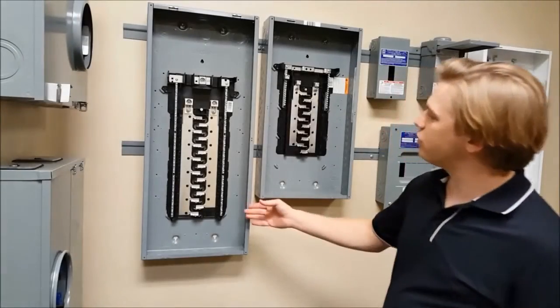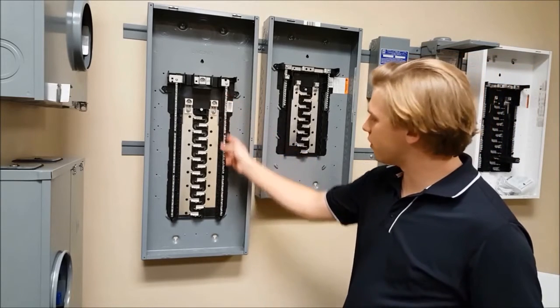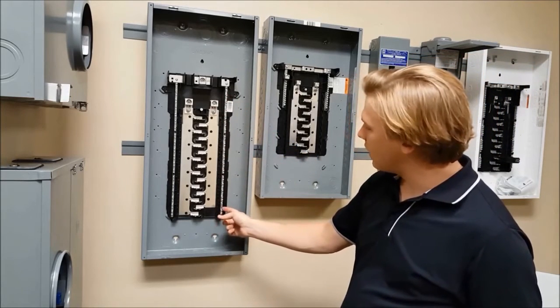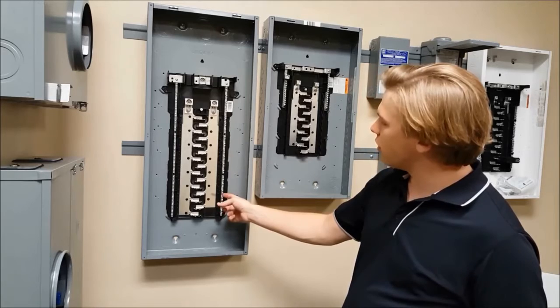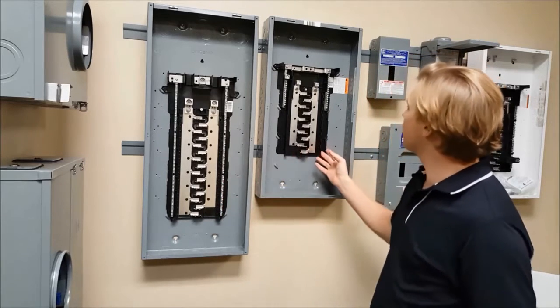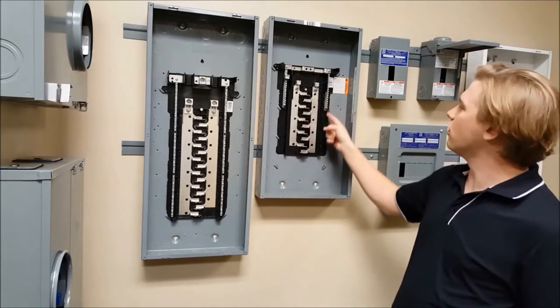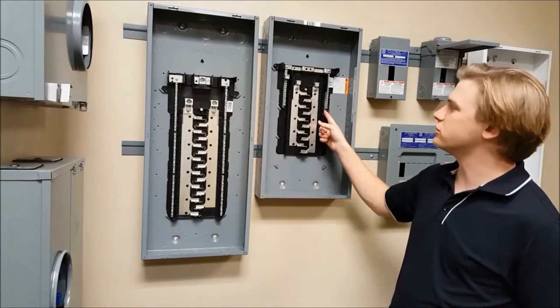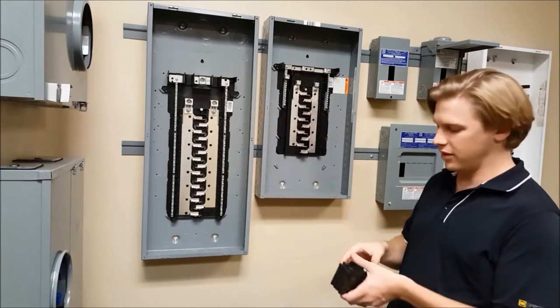You'll see in the plug-on neutral panel that the neutral bar runs all the way to the bottom and has the spaces in it where the plug-on neutral rail will connect. On the non-plug-on neutral version, the neutral only goes as long as it needs to accommodate all the spaces in the panel.